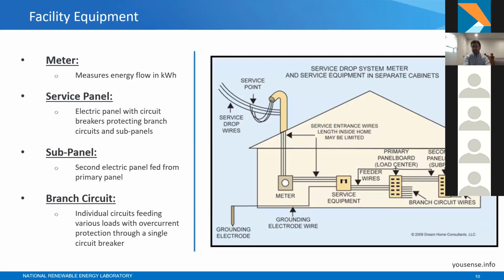And then switching things back to the facility perspective, just to get your bearings here, the branch circuits and subpanels and service panel here are all lined out. And this is where you can see up at the top left of the picture, the service drop comes in from the utility and goes through a meter, some service equipment and primary panel board. These primary panel boards or service panels are really where those circuit breakers would be positioned and where you'd be potentially upgrading them. These are where most of the upgrades your facility would be considerate of.